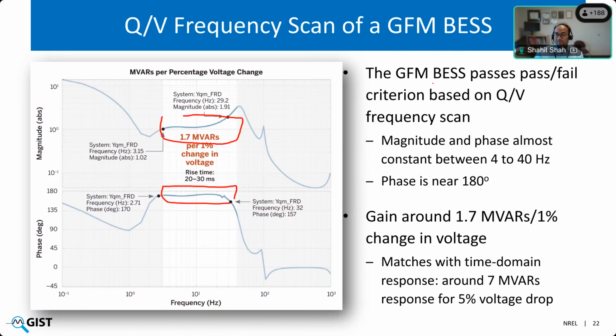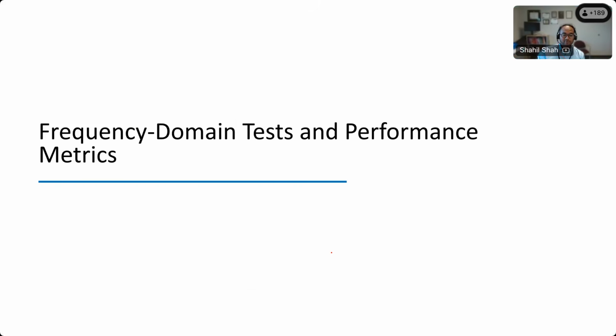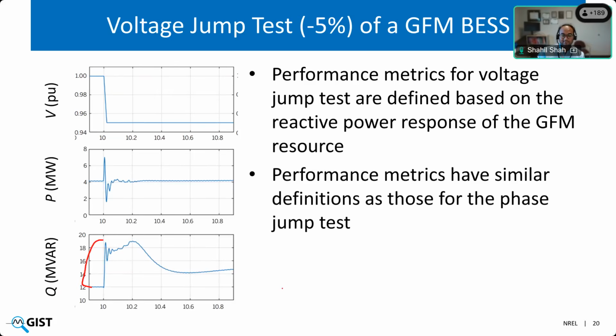So this particular grid forming BESS passes through the Q by V frequency scan criteria. I think there's a typo here. Oh, no, it's not actually. I misread it. The phase is closer to 180 degrees. The gain is more or less constant between 4 to 40 hertz. And the gain is 1.7 MVARs per 1% change in the voltage magnitude. Again, as I said, it matches with the 7 MVAR response for 5% voltage drop in the time domain response, which I didn't talk much about, but it's particularly on this slide.